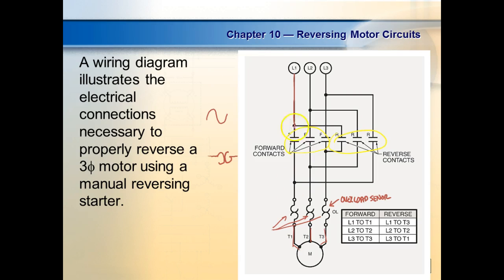So what we do is we bring in our 3 lines. Here comes Tennessee Valley Authority. We bring them into our contactor, into the ones labeled L1, L2, and L3. And then we put jumpers here. We take these over and go to L1, L2, and L3. So you just jump across the top. You just jump them together, right? Does that make sense so far?